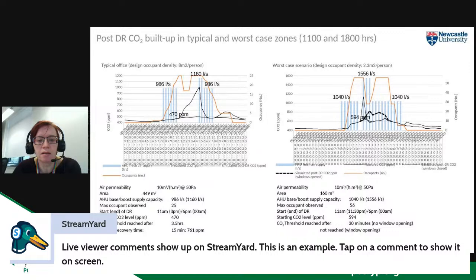The worst case on the right-hand side shows the air handling unit only being off for half an hour. So there's only one blue bar missing, a half-hour period. And then the carbon dioxide level shoots up past 1,000 parts per million, and the air handling unit has to kick back in. Also notice that the air handling units, when they come back on, are slightly boosted, so they're offering slightly higher air change rates in order to clear the air in the space.